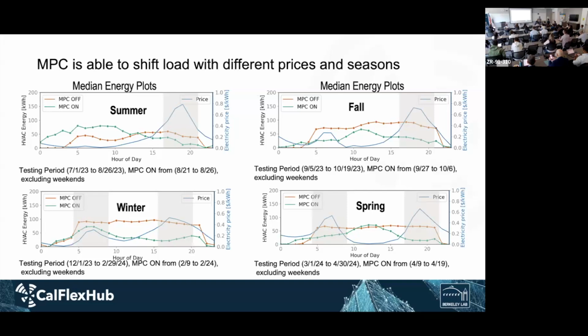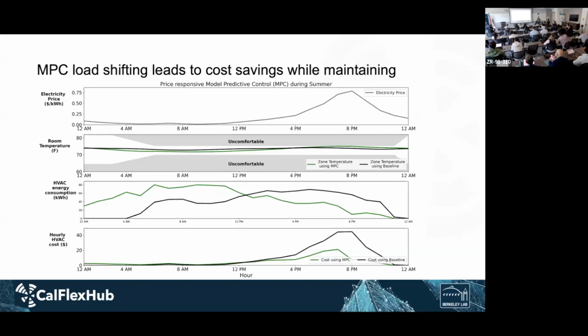And if you can go to the next slide, I'm going to show you an example of a typical day of operation for summer. The chart at the top is the electricity price, and on the x-axis you have the hours of the day from midnight to midnight. The second chart instead is the average temperature in the whole building, and in gray are the, let's say, areas that are considered uncomfortable. Those are the temperature set points. In black is the baseline controller, and in green is the MPC.